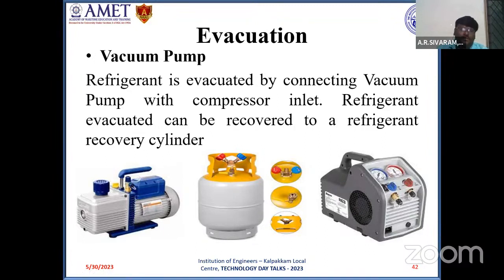Normally they check the vacuum before charging refrigerant. That is, they maintain negative pressure for a certain span of time before charging. If the negative pressure is maintained, the system is free from leaks. If it is very difficult to sustain negative pressure, it means a leak is still present in the system, due to which air has leaked inside and the pressure has increased. So a vacuum pump is used for evacuation of refrigerant.